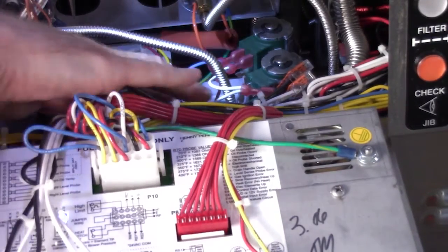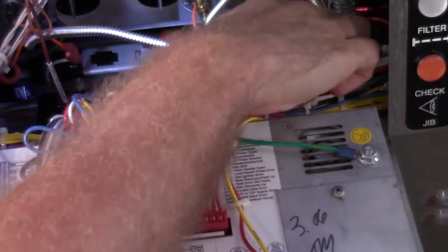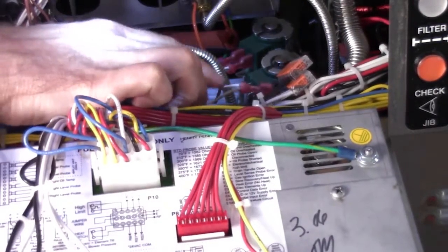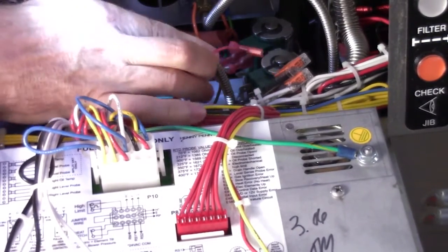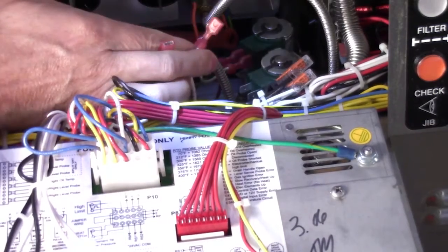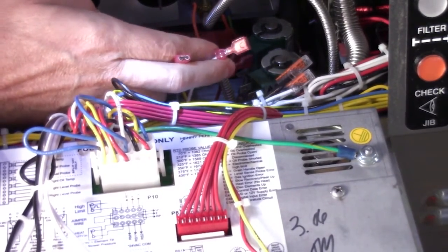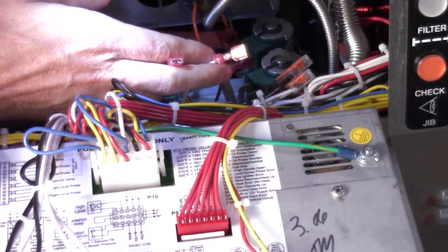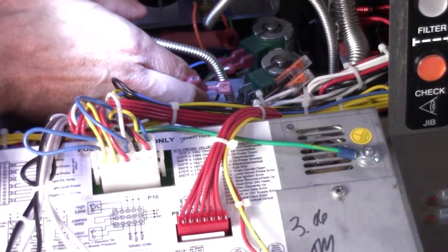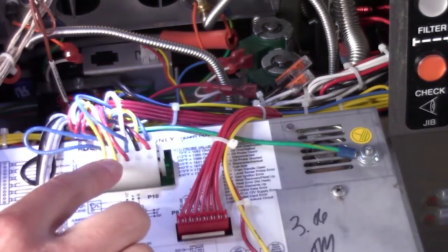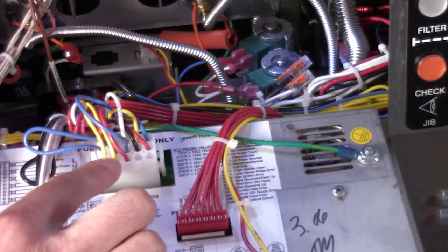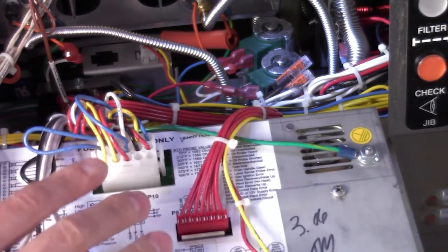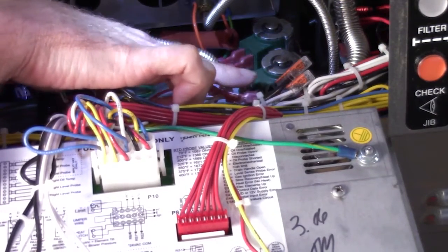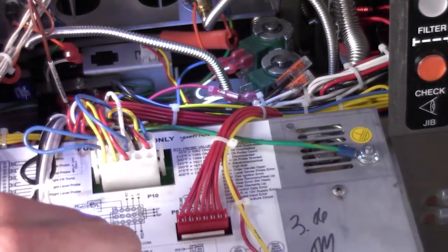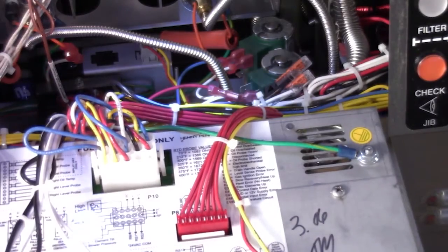So I've already unhooked the wires here, and that's why we're not getting the heat to come on, but it's these two wires. You can go ahead and stab into the wires, so you can stab the leads of your voltmeter into the wire. Why is this important to do it that way? Well, let's say I had these hooked up, and I'm checking my voltages from here back at the control, and I'm seeing a drop in voltage. It doesn't mean that the control board is bad. It's a good possibility that this coil over here is bad, and it's pulling the voltage down and causing the issue.